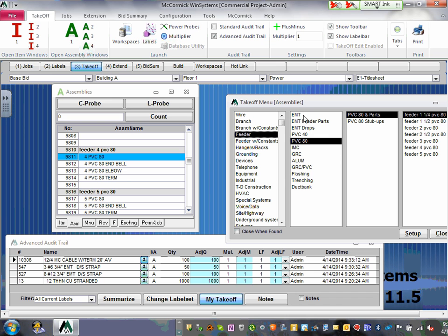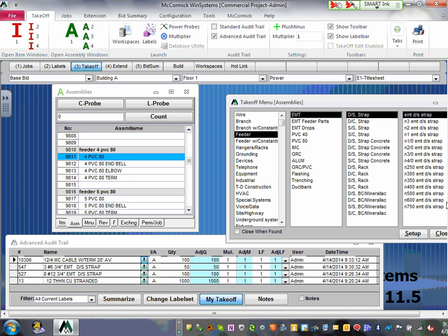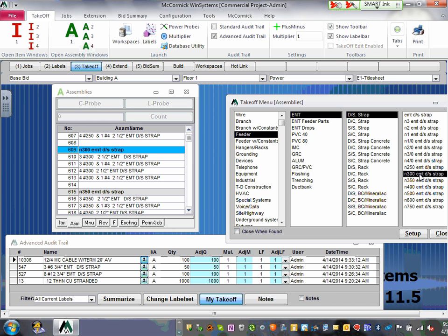So let's go check, guys, EMT. Look, EMT feeder. Okay, look at this. If I need to go pull 300 kcm, can you guys click on 300 kcm? Now I'm looking right here. I have a feeder. That feeder can go up to 3 conductors, 300 kcm. Can I get you guys to understand the difference between feeders and branch circuit? They're all identical. The only difference, Karen, is bigger, larger conductors. That's all. So if I have 3 conductors, number 300 kcm, it's already sized to fit in 2.5-inch EMT conduit with a strap. Here you go.